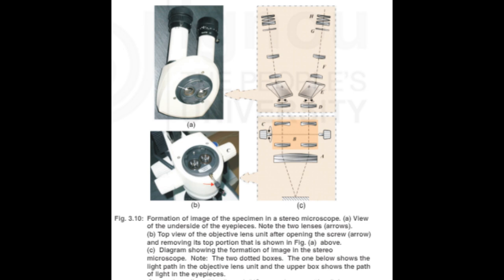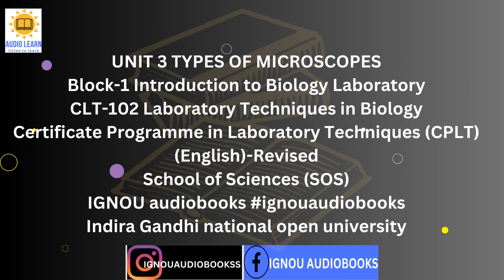This microscope usually has a prism placed in the light path between the objective and the eyepiece that inverts the already inverted virtual image so that the observer sees the object in its true orientation, that is, left, right and up, down are seen as they exist in the object. Stereo microscopes are therefore useful where depth perception and specimen orientation are required in micro dissection of tissues.